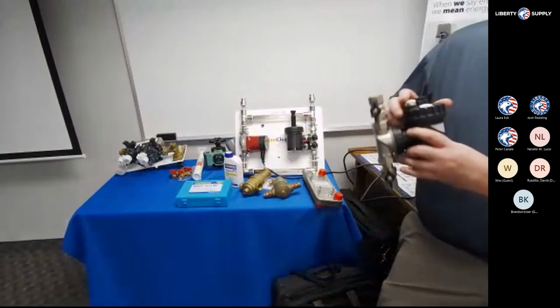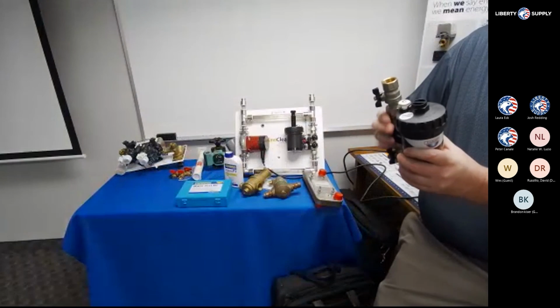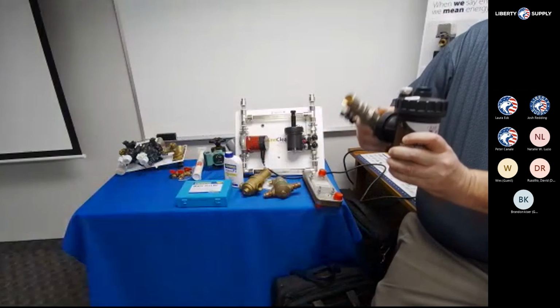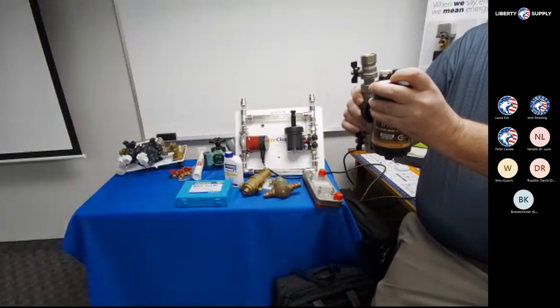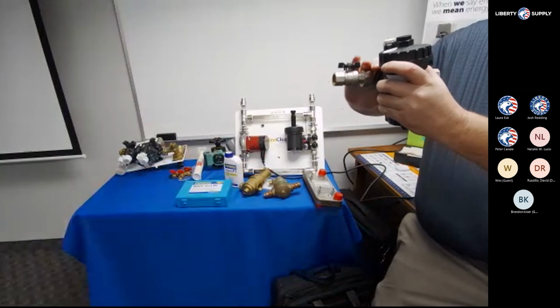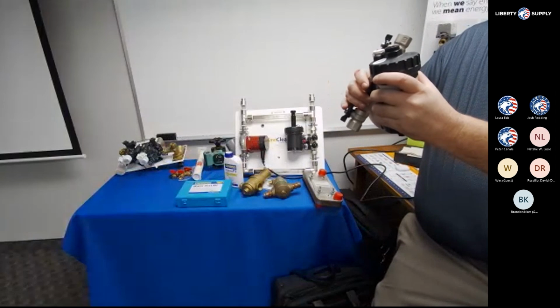This is an example of a standard magnetic filter we have here. We're talking about being able to adjust the position. We need to keep this canister in the vertical position, but we can adjust the piping, so if I've got horizontal piping, or vertical piping, or it's on an angle.